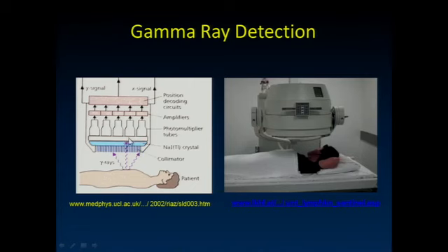By detecting the amount of light seen by the adjacent photomultiplier tubes, for instance, this tube here is going to see the majority of the light from this event, and the one here a smaller percentage. I can interpolate where the event occurred by knowing how much light is detected by the few surrounding tubes.